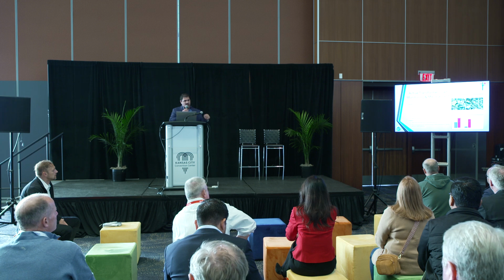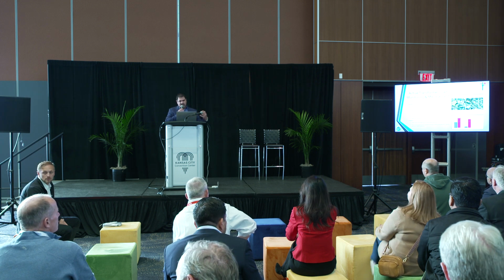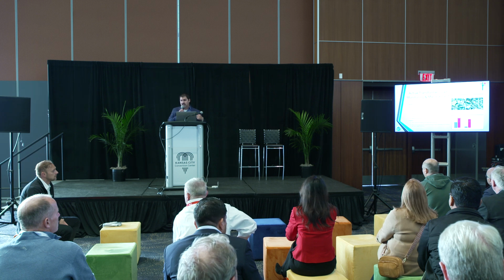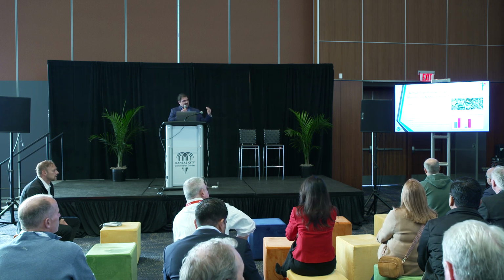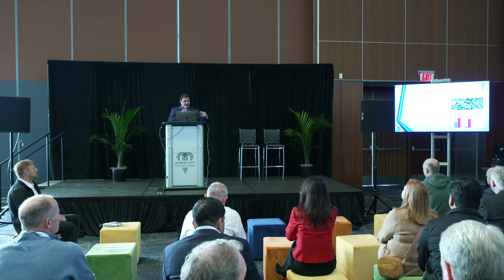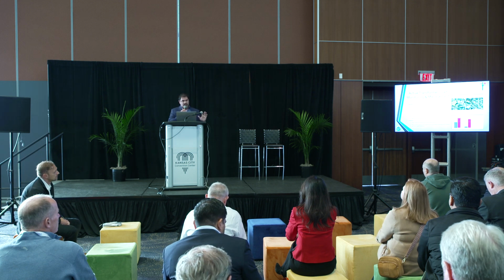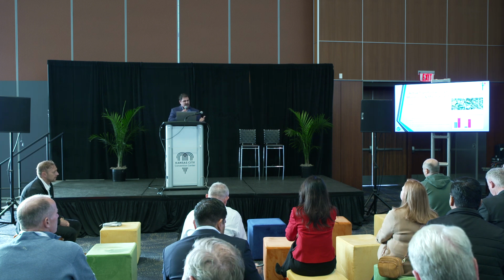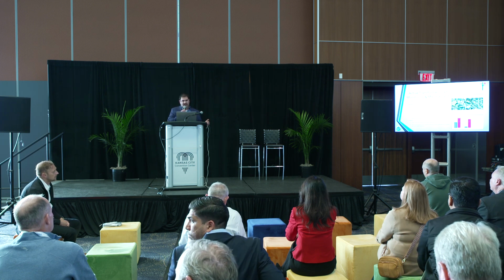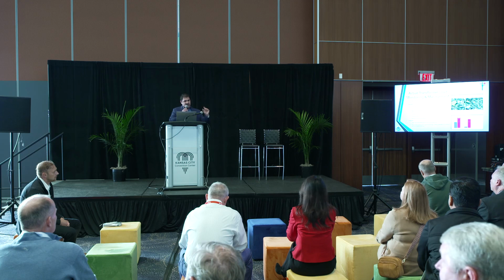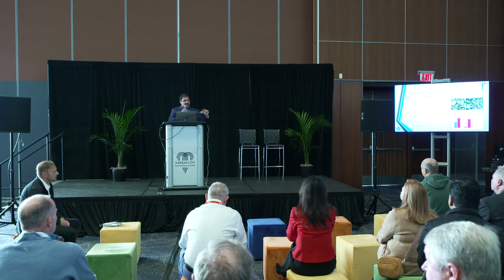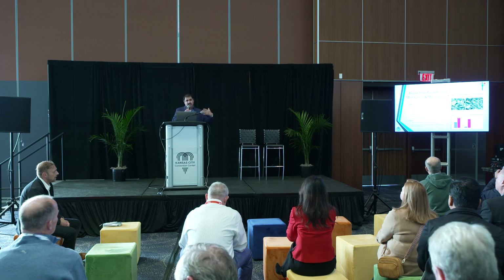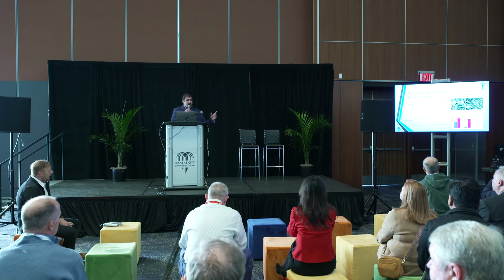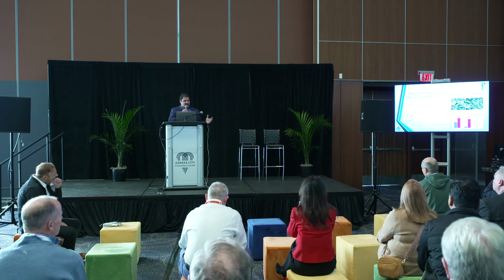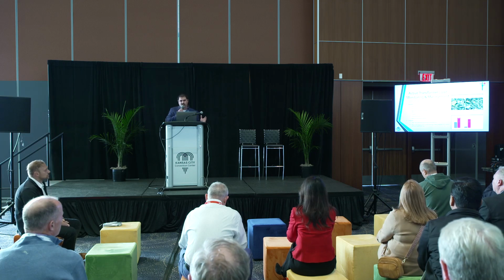This is effectively ground zero when it comes to how we're managing the grid. And so because we can touch all those devices on that same transformer, we have the ability to aggregate the data amongst all those electrical peers in real time. And because these devices are communicating over PLC, they're sharing a bunch of different parameters, not just loading: active energy, reactive energy, demand, voltage, min-max, and average. You could push this data up to control systems in one interval of data in a consolidated packet from a single device, meaning that you're better leveraging the capacity of the network to provide even greater visibility than what you'd otherwise be using in traditional AMI 1.0. So this is literally SCADA level capabilities of visibility down to the distribution transformer.